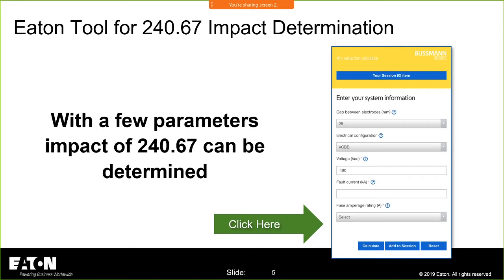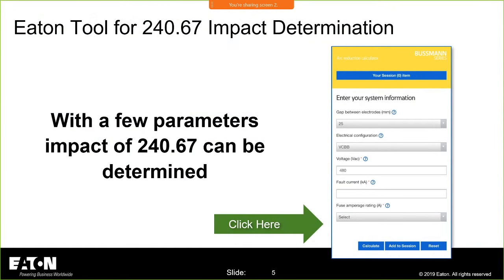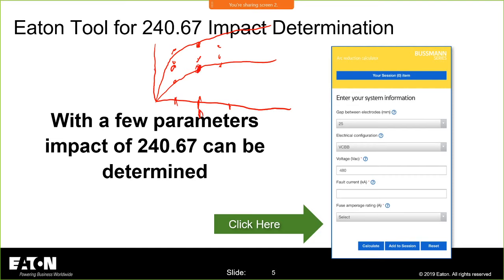So if you think about a graph, and you have data points for different values of fault currents, and you say, well, my arcing current was here, my arcing current was here, and when I increased it, my arcing current was here. You have all of these data points, and then you can draw a line on the bottom edge and a line on the top edge. And so you know that for any bolted fault current, you're going to have an arcing current that's going to be a minimum and a maximum. So it gives you your range.